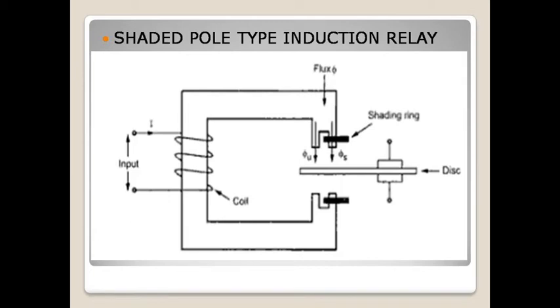The shaded part produces the shaded flux which lags 90 degrees from the unshaded flux. So there are two fluxes—unshaded flux and shaded flux—which have a phase lag between them of approximately 90 degrees.